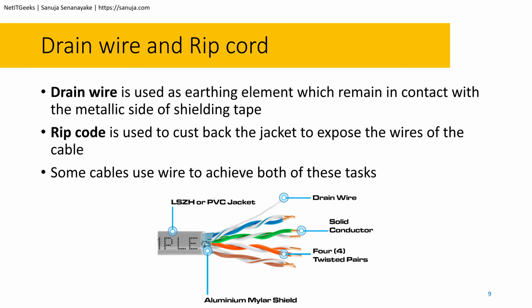Drain and ripcord. So drain wires and ripcords are two different things, but sometimes can be the same. So you could have a ripcord that is also acting as a drain wire. A drain wire is used as an earthing element which remains in contact with the metallic side of the shielding tape. In other words, if you have a cable with a metallic shield like this, it might have a drain wire that can be grounded because now there's more metal exposed in this cable outside of the twisted pairs. So you will have a drain wire like this that will be in contact with aluminum or other metal shielding, and this drain wire is probably going to be metal. Why? Because then you have the ability to ground this cable, especially in outside installations.